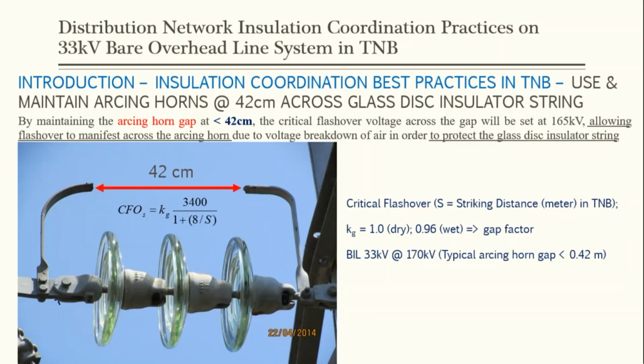We allow breakdown of the air in order to protect the solid insulation of the overhead line system. Okay, so we have this formula, the critical flashover voltage, with a striking distance S in meters, and then we have kg, where kg is the gap factor. During dry condition, we use 1.0, and during wet condition, we use 0.96. And typically, the BIL for our 33 kV is 170 kV. So that's why we set at 42 cm or below, because we want the gap to have a flashover, or a CFO, at 165 kV, to allow that flashover to occur across the arcing horn gap, to protect the glass disc insulator.